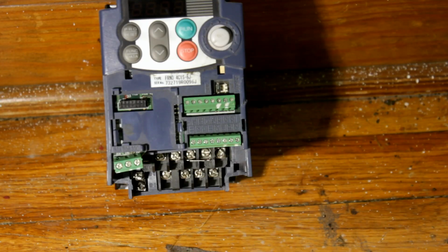So there's another small variable frequency drive, and I don't know if you can see that, but those three terminals on the top there, the ones with the jumper, that's P1, positive, and then to the right of that is the negative. Again, that jumper you pull out to put a choke there, but otherwise it has to be in place. So if you see that jumper there, that's where you connect the positive, and then to the right of that, it's going to say negative.